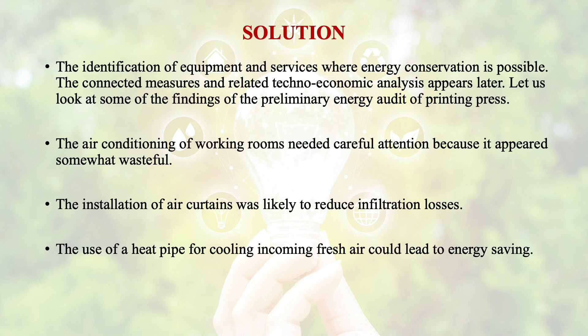If we talk about the findings of the preliminary energy audit of a printing press, we could see the air conditioning of working rooms needed careful attention because it appeared somewhat wasteful. The installation of air curtains was likely to reduce infiltration losses. Use of a heat pipe for cooling incoming fresh air could lead to energy saving. The efficiency of the cooling tower could be improved by replacing the existing fan with an FRP fan and lower HP motor. For certain blowers of air washer units, the driving motors were kept inside the cooled air path, adding unnecessary heating load. The motor should be kept outside the rooms.